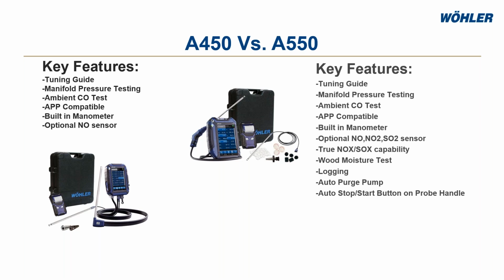With the A550, depending on what kit you have, you'll have some of these features and may not have others. Some kits have a tuning guide, manifold pressure test, ambient CO, app compatibility, and built-in manometer. Some are going to have an option for NO, NO2, SO2, so if you have that true NOx or SOx testing requirement, the A550 gives you that capability. You're also going to have a wood moisture test, which is nice if you're testing wood fire boilers, so you can test the moisture level in the wood you're putting in.